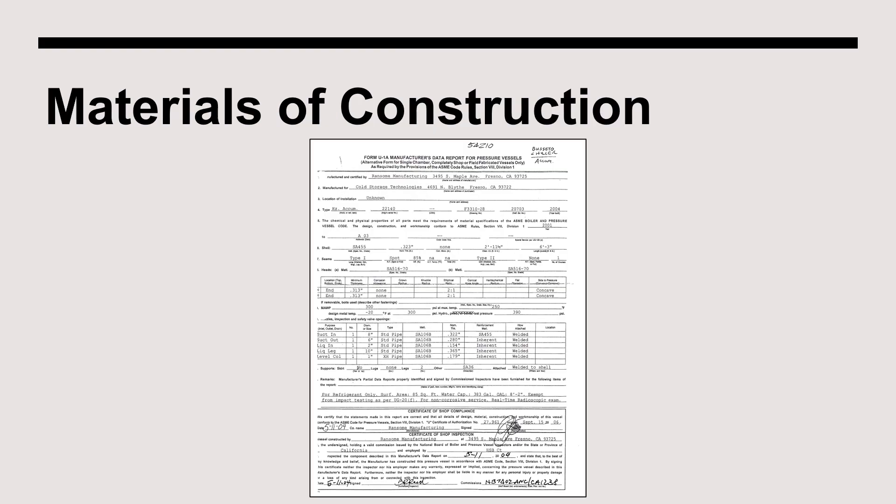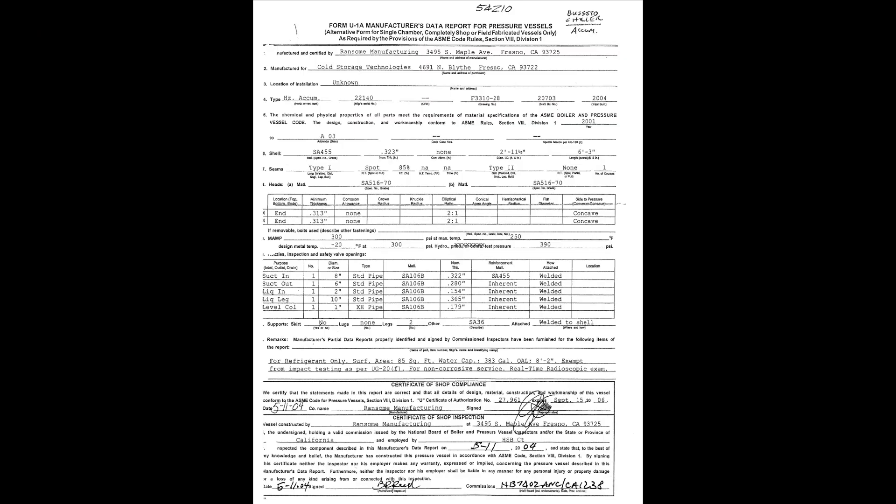When documenting the materials of construction for a suction accumulator or any pressure vessel, the key document is the Manufacturer's Data Report. A closer look shows that the U1 form describes the steel specification and thickness for both the head and the shell of the vessel. The bottom of the page includes a listing of all vessel connections, including the size, grade, and schedule of the nozzle.